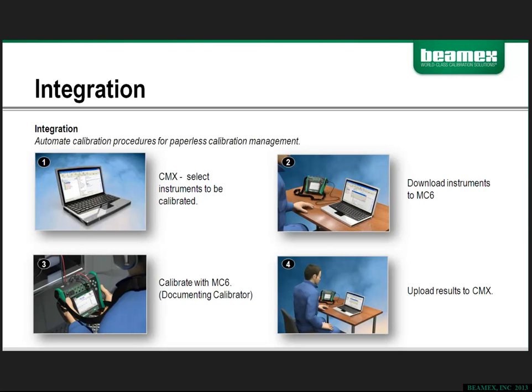Once they're in there, you can take your MC6 out into the plant and perform these calibrations, and all of the information pertaining to that particular instrument, including the calibration procedure, are stored inside the MC6, at which point you bring up that instrument and bring up the calibration procedure, which shows you directly exactly how to hook up the instrument to the MC6 calibrator. And it shows you step-by-step, takes you through the process of running the calibration.